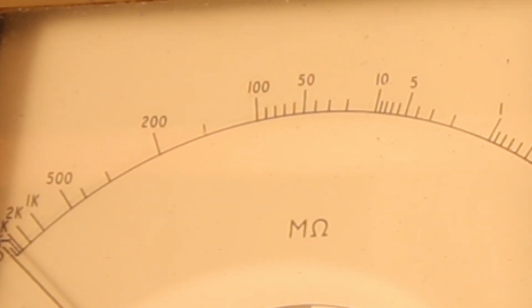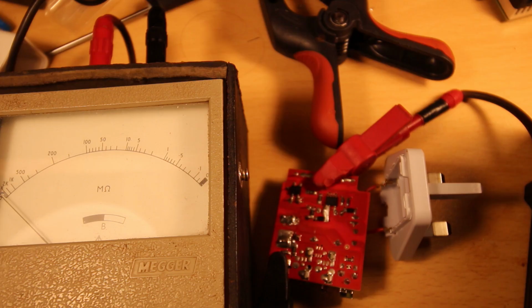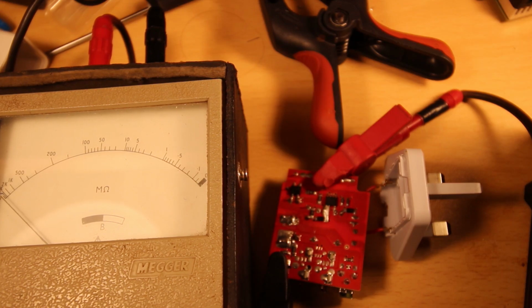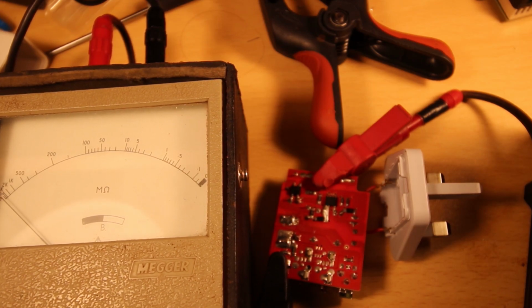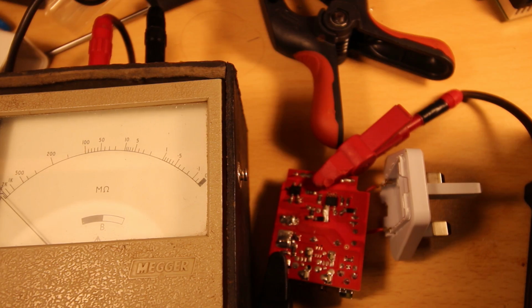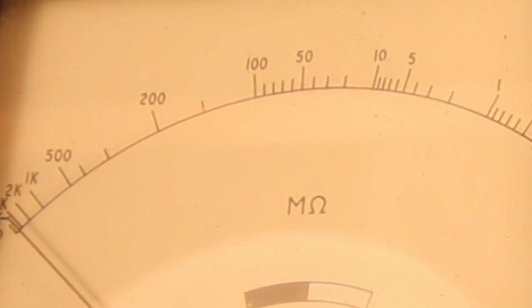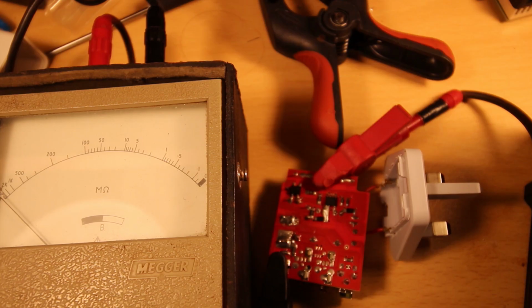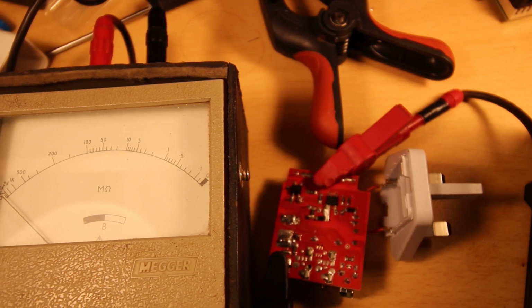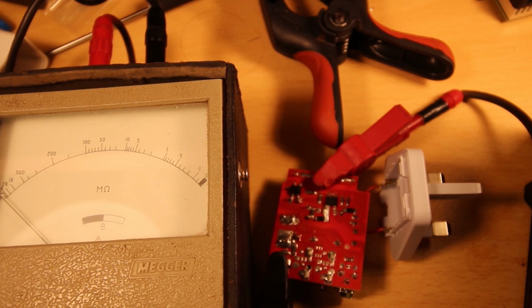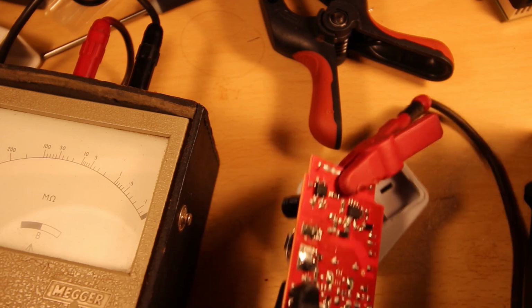It's reading 10,000 megohms, and we'll do it on 1000 volts and see what we get. We get 5,000, but because of the range of this meter, that's doubled, so 5,000 times 2 is 10,000 megohms again. So this passed its isolation checks.